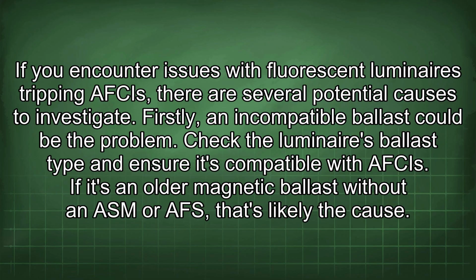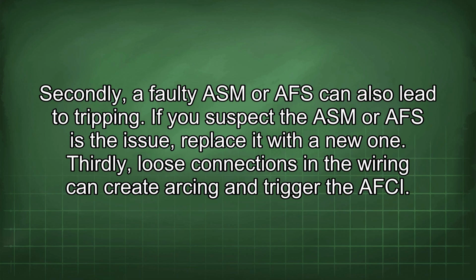If you encounter issues with fluorescent luminaires tripping AFCIs, there are several potential causes to investigate. Firstly, an incompatible ballast could be the problem. Check the luminaire's ballast type and ensure it's compatible with AFCIs. If it's an older magnetic ballast without an ASM or AFS, that's likely the cause. Secondly, a faulty ASM or AFS can also lead to tripping. If you suspect the ASM or AFS is the issue, replace it with a new one.